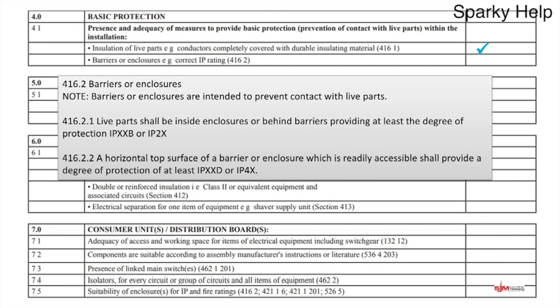Barriers and enclosures are the main ones that apply, because remember we're trying to stop someone physically touching something. There are two sets of IP ratings ultimately that we apply, and barriers and enclosures are intended to prevent contact with live parts. So live parts shall be inside enclosures or behind barriers, providing at least a degree of protection of IPXXB or IP2X. What is that? That's roughly the size of your little finger. So we shouldn't be able to get your little finger inside an enclosure.